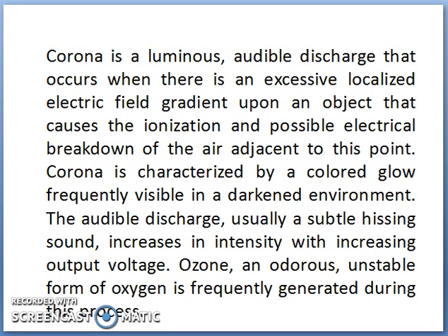called as corona. So, corona is a luminous audible discharge that occurs when there is an excessive localized electric field gradient upon an object that causes the ionization and possible electrical breakdown of the air which is adjacent to that point. Corona is characterized by a colored glow frequently visible in a darkened environment.